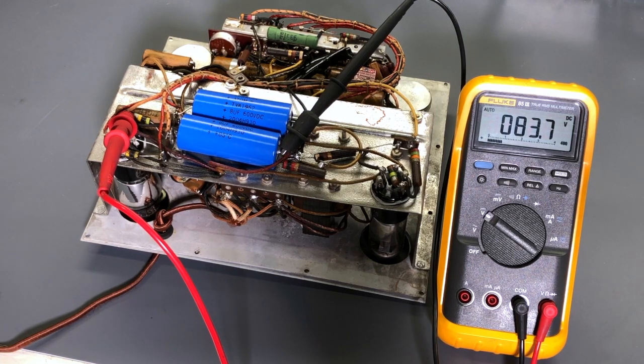Okay, the capacitor tester has been on now for about a half an hour, and the DC voltage has stabilized around 83.5 volts, 84 volts, right in that range. So now I'm going to increase the AC voltage upwards towards the normal 120 volts AC that the unit would normally operate at. In the half hour that it's been on, there's been no issues. The voltage looked good, it's been stable, and nothing has become warm or overheated, no issues like that. So everything has been looking very good up to this point. So now I'm going to begin increasing the voltage some more.